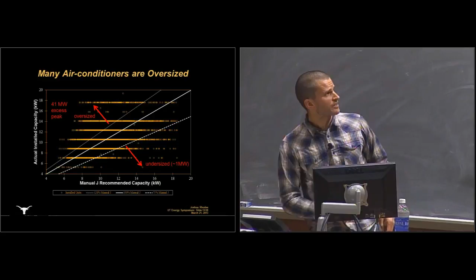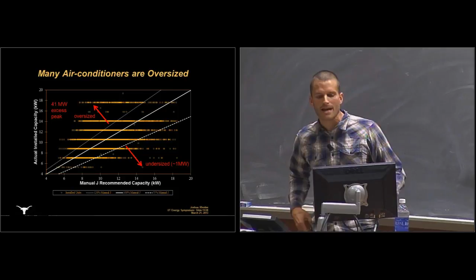The dotted line is 120% of Manual J, because for rounding errors, since you can't get something like 4.57 tons of refrigeration, you can only get 4.5 or 5, we called anything above 120% oversized. The dashed line is 75% of the Manual J sizing calculation, because studies have shown the industry standard actually oversizes somewhat, and about 75% of what it recommends is adequate to meet the load. This is where we get 41 megawatts of excess peak. Interestingly, if we upsized units that seem underperforming or unable to meet the load, it would actually add about a megawatt of peak power demand to the grid.